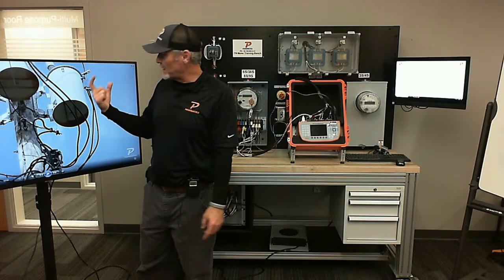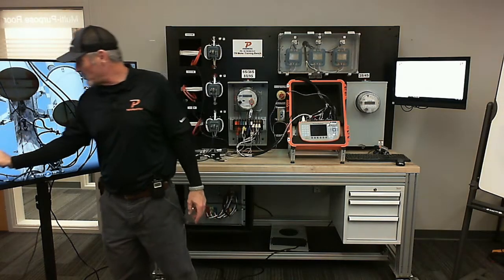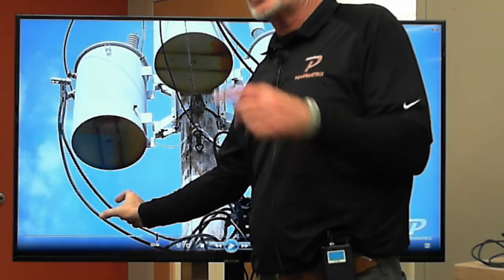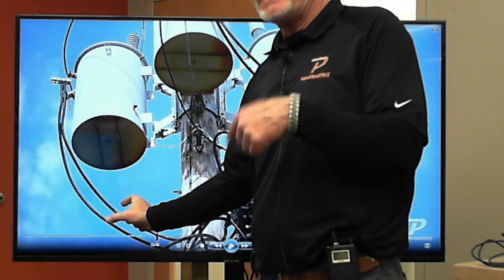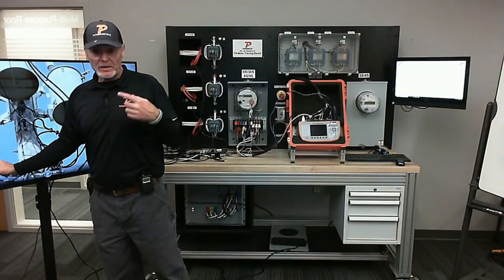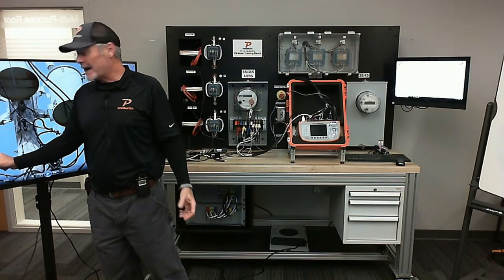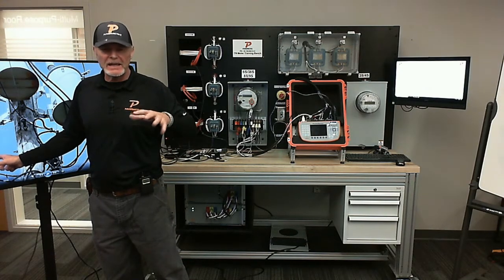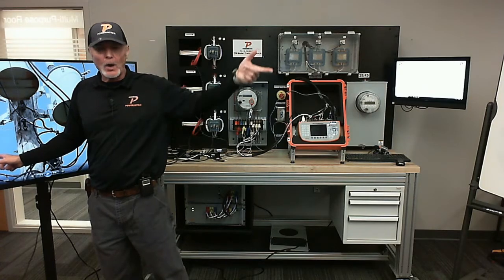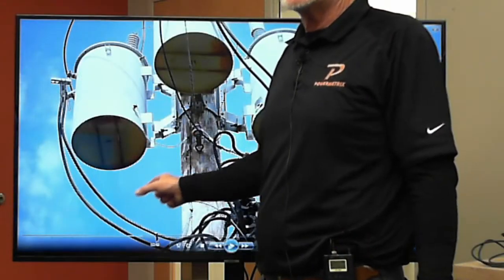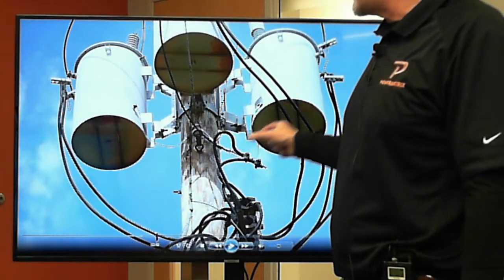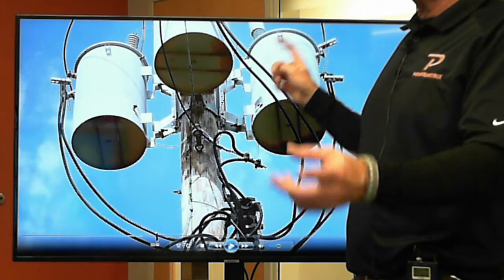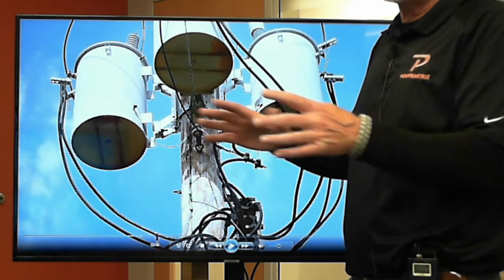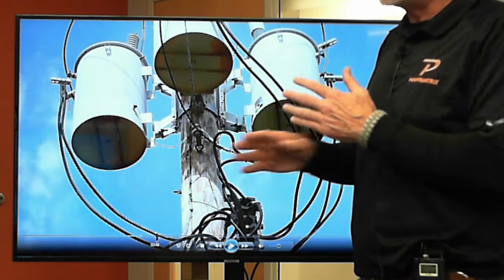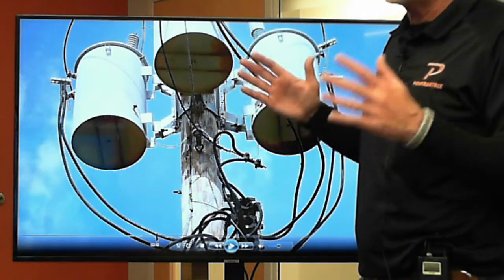So when I take my high volt probe, put it on one of these, and it tells me cross phase when I'm supposed to be testing A phase, then I know I'm actually on C phase. At that point folks use different techniques - they may start the test over, or just go ahead and finish, testing B and then A phase, and start the thing over again. It's totally up to you, but either way you've now determined which phase is which.